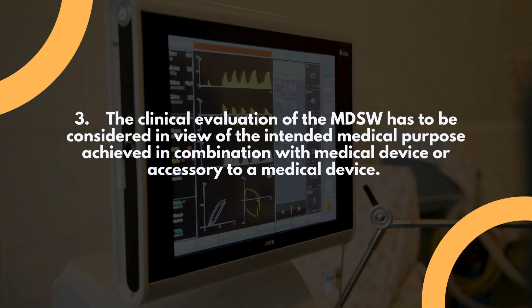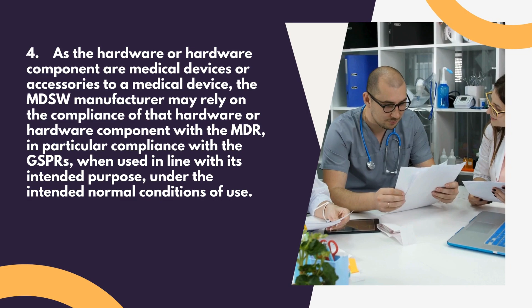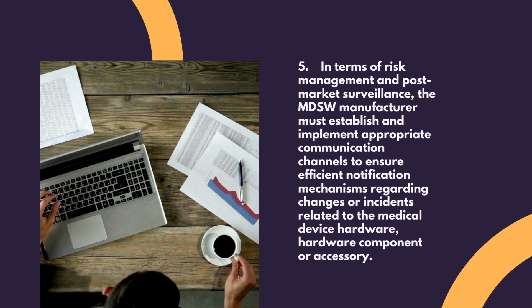The medical device software manufacturer may rely on the compliance of that hardware or hardware component with the MDR, in particular, compliance with the GSPRs when used in line with the intended purpose under the intended normal conditions of use. In terms of risk management and post-market surveillance, the medical device software manufacturer must establish and implement appropriate communication channels to ensure efficient notification mechanisms regarding changes or incidents related to the medical device hardware, hardware component, or accessory.